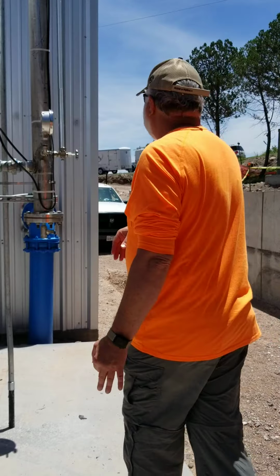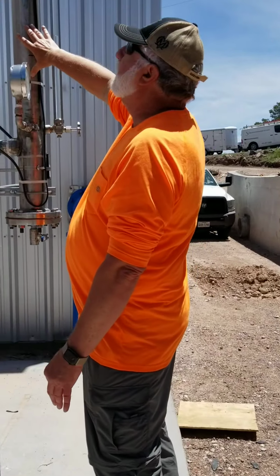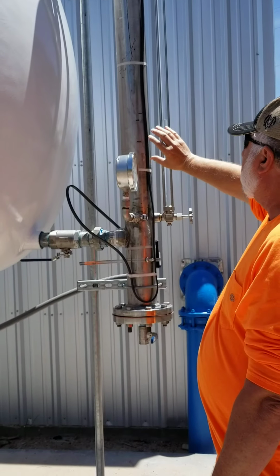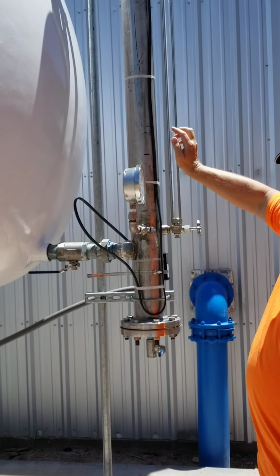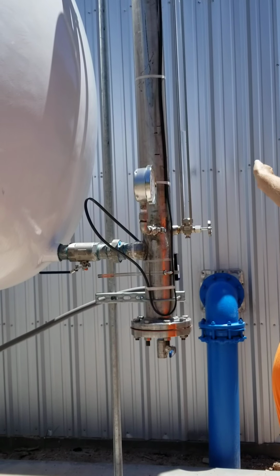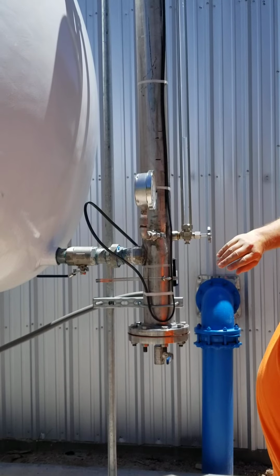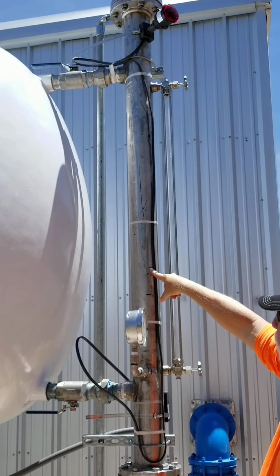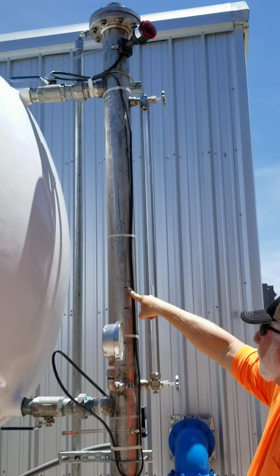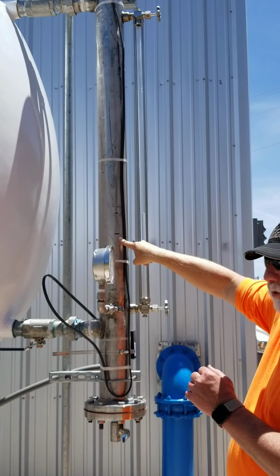So you have some marks here. There are probes in this probe bottle tube that control the add-air solenoid valve, which allows air from the air compressors to come into the tank. You have a mark here where it starts adding air, and this is where it stops. And this is your ground reference.